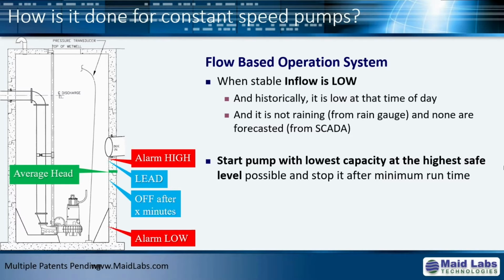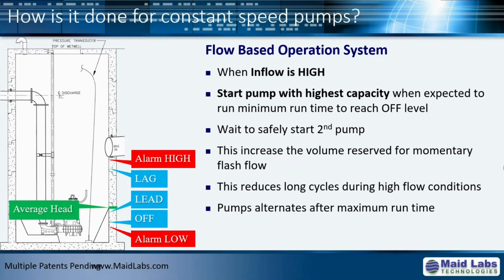But you do that when it's safe to do so, and to know it's safe you need real-time flow. If the flow coming in is high, and you know it in real time, you know your pump will be running for 2 hours. If you're waiting to start them at the lead level, why wait? As soon as you know your pump will be running at least 2 minutes or more, start your pump right away. Otherwise it will take way more time before you reach the lag level where you start your second pump, and we know that 2 pumps together are not really very efficient.